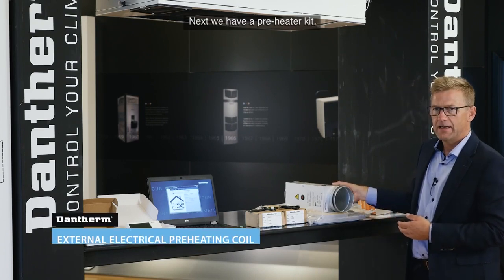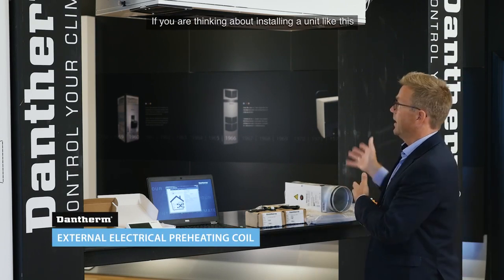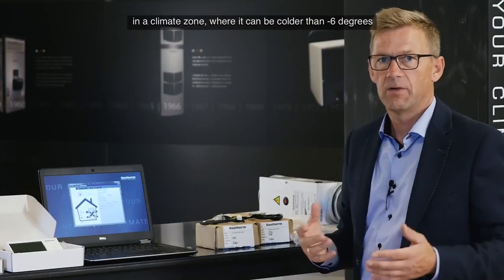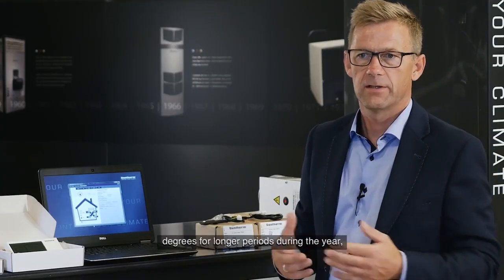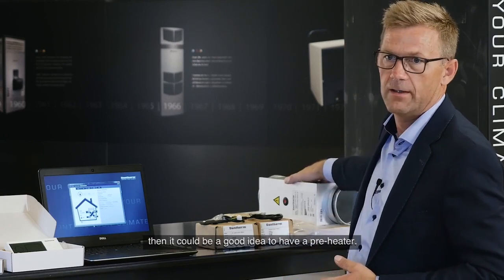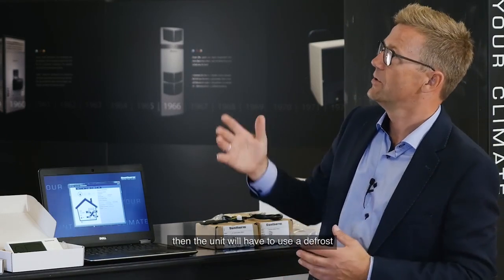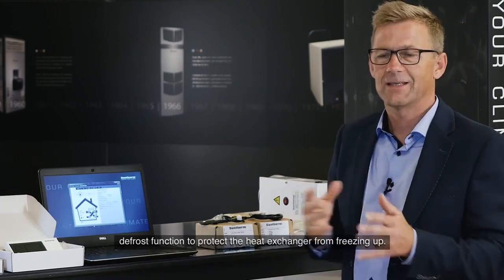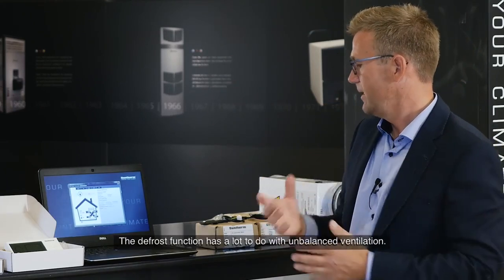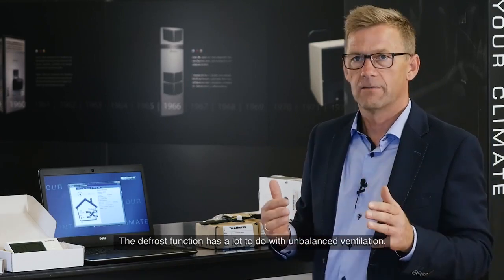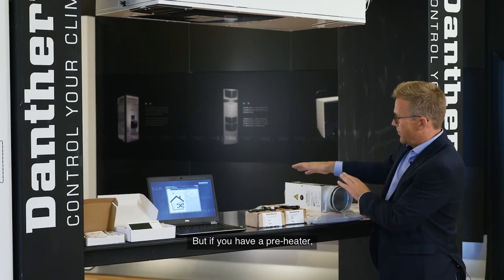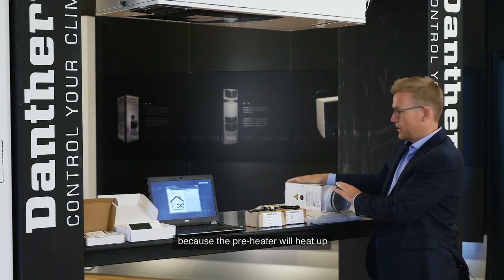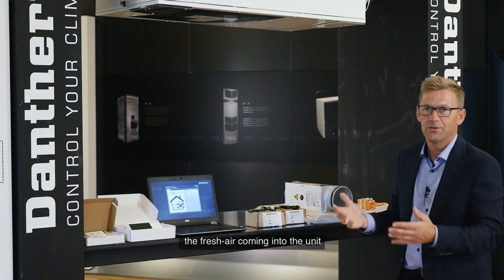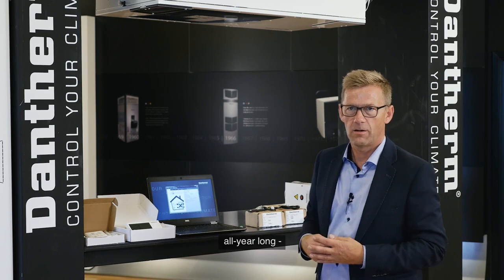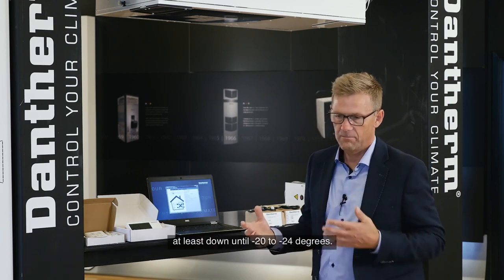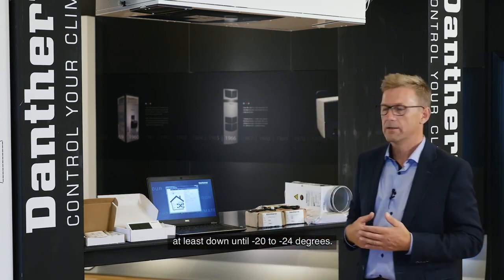Next we have a preheater kit. If you would like to have a unit like this installed in climate zones where it can be less than 6 degrees for longer periods every year, it's a very good idea to have a preheater. Because if you don't have a preheater, the unit needs to use a defrost functionality to protect the heat exchanger from freezing up, and that defrost functionality has to do with unbalanced ventilation. Whereas if you have the preheater, there's no need to use unbalanced ventilation, because the preheater will heat up the fresh air coming into the unit, and it will be safe, balanced ventilation all year long, at least until around minus 24 degrees.